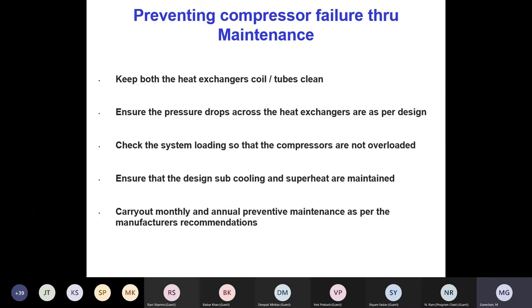How can we do this? I have always said, there are two heat exchangers, the condenser and the cooler. It could be air cooled or water cooled. The most important thing is that both must be clean, inside or outside. Air cooled means outside; water cooled means inside. Cleaning must be done properly, because nowadays manufacturers are making beautiful heat exchangers with internally rotating grooves. If scale forms in all those, within 3-4 months the whole 10-15% efficiency is gone.